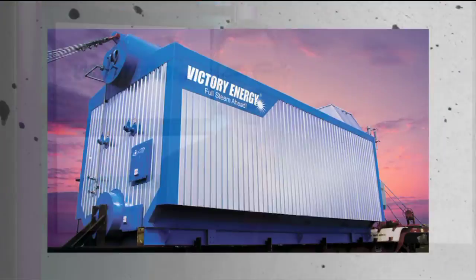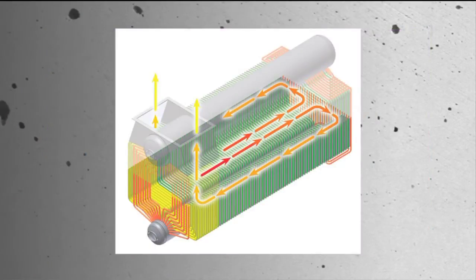So how does a company choose the best product for their needs when it comes to steam boilers? Consider the benefits. For example, a water tube boiler has the edge over a once-through design. The quality of the steam in a natural circulating water tube boiler is near 100%, as opposed to some saturated once-through steam generators, also known as OTSGs.